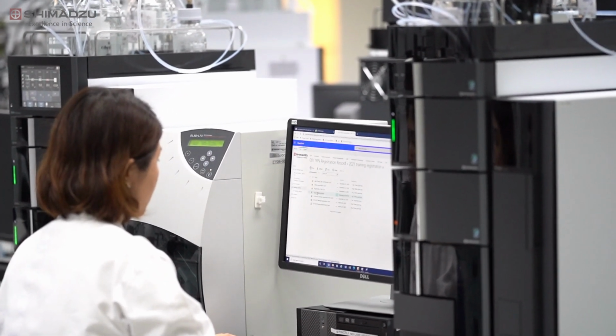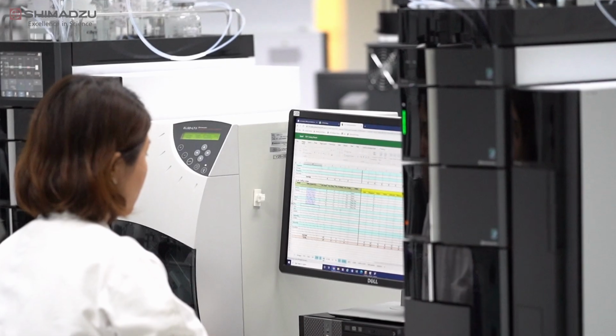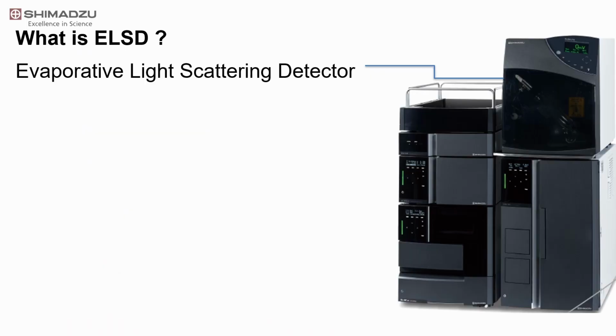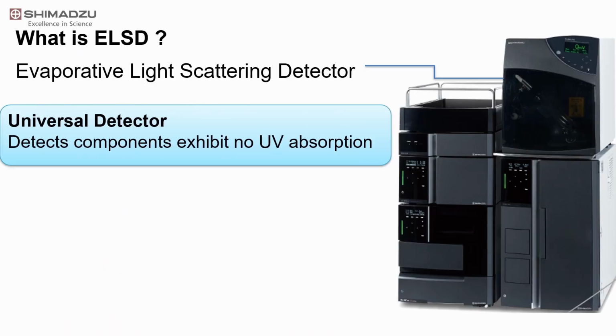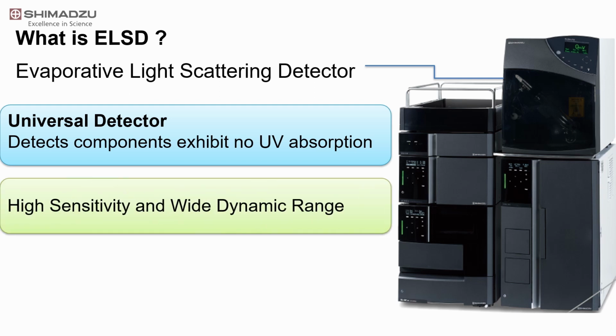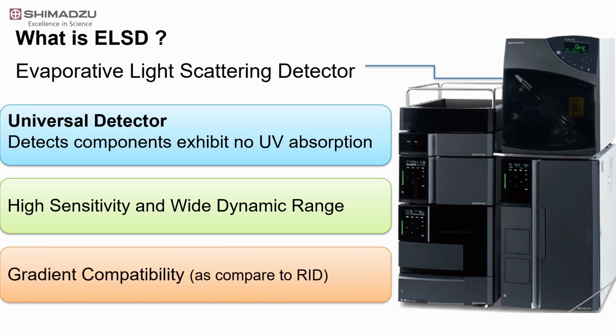What is ELSD? ELSD stands for Evaporative Light Scattering Detector. It is a universal detector that can detect compounds that exhibit no or poor UV absorption. Shimadzu ELSD LT3 offers both high sensitivity and a wide dynamic range. Unlike refractive index detectors, ELSDs are compatible with gradient elution.